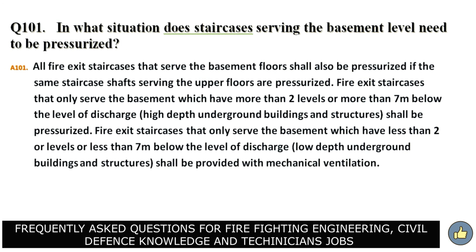In what situation do staircases serving the basement level need to be pressurized? Answer. All fire exit staircases that serve the basement floor shall also be pressurized if the same staircase shafts serving the upper floors are pressurized. Fire exit staircases that only serve the basement, which have more than 2 levels or more than 7 meters below the level of discharge, high depth underground buildings and structures, shall be pressurized. Fire exit staircases that only serve the basement, which have less than 2 levels or less than 7 meters below the level of discharge, low depth underground buildings and structures, shall be provided with mechanical ventilation.